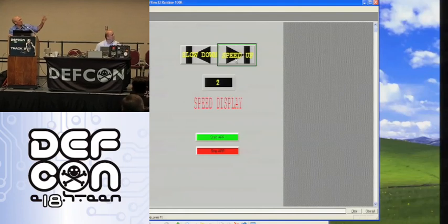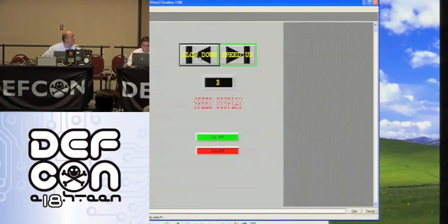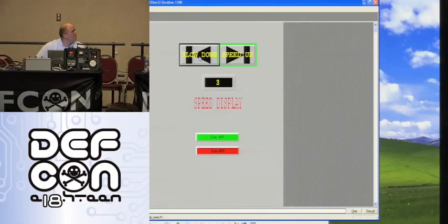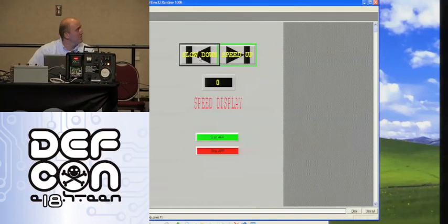All right, well, now we're just going to show that this exploit works. Paul, can you slow it down for us? And speed it up one more time for us. Now this is pretty dangerous. When you get direct control over a component as powerful as a VFD, you're directly controlling how much material is forwarded to some other area of the process, whether it be steam or coal or slurry or whatever. So both upstream and downstream components can be affected by this. This is a very dangerous situation.